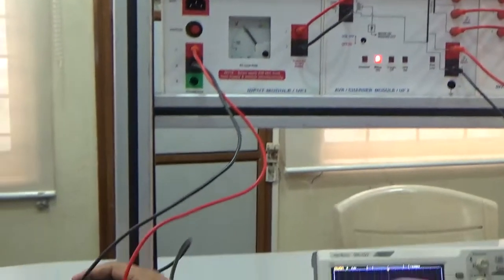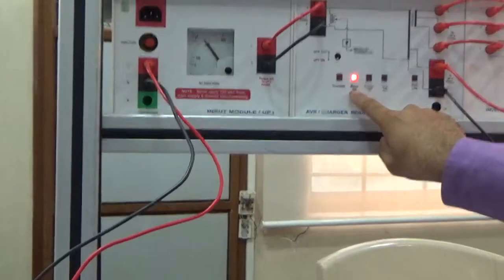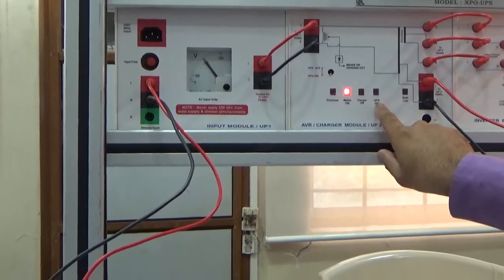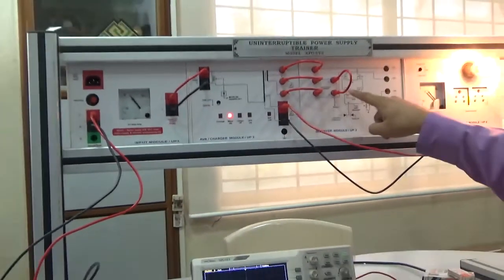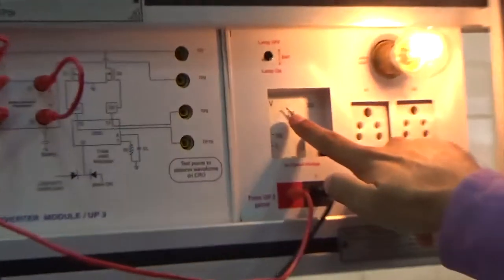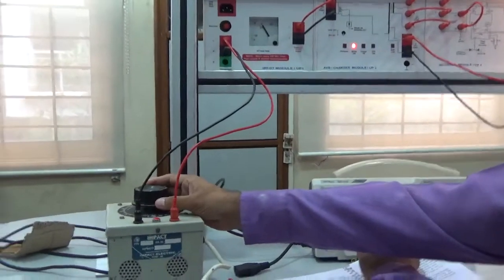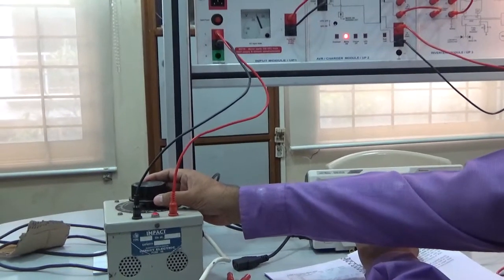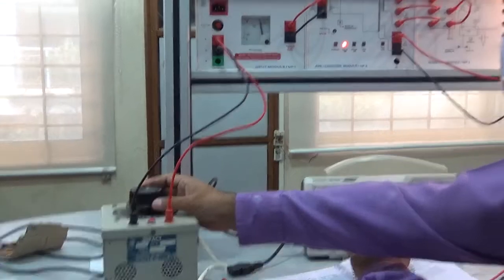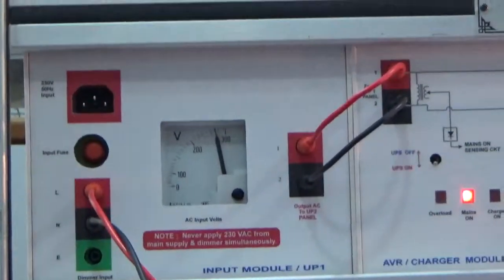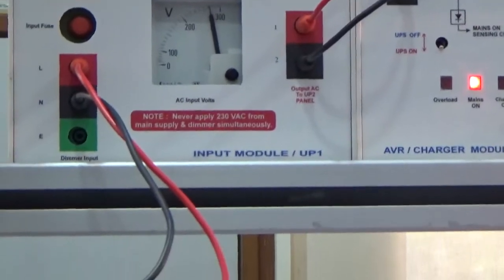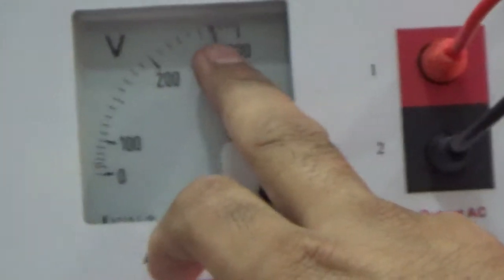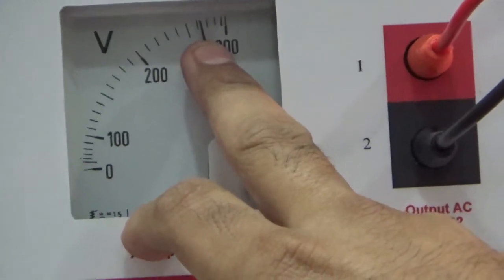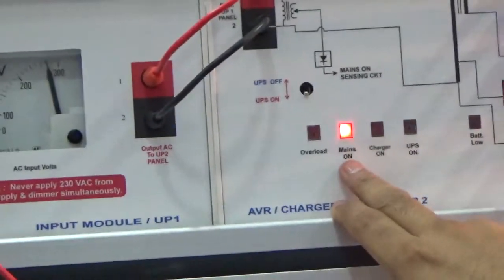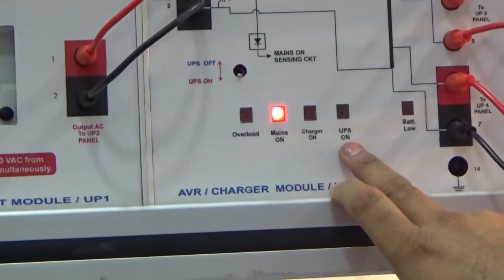Again we will increase to 200 volt. Again it switches to mains on from UPS on, and again the battery will start charging, and here you will get mains voltage. Now again we will increase the input voltage. Here the dimmer limitation is 260 volt, but at 270, 275 it will trip as an over voltage, and again this mains on will be off and UPS on will be on.